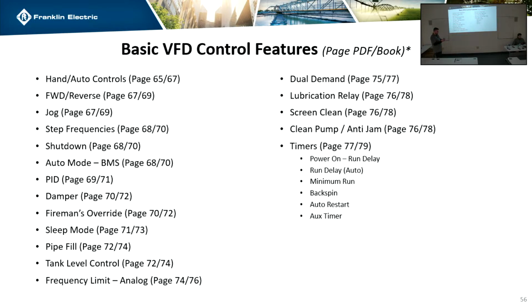Let's see, step frequencies. So this is for people that want the drive to go at a certain speed based on a contact. So they flip a switch, they want it to go 30 hertz, a different switch 50 hertz. There's no PID loop, there's none of that. Just if I push this button or if I flip this switch, I want it to switch to this speed. That chart, where we have 4 inputs, but we have 15 different speeds, and the chart just tells you the binary on-off of how to control each one.